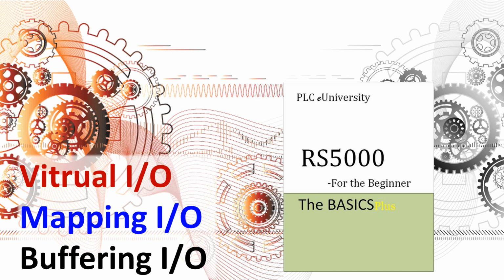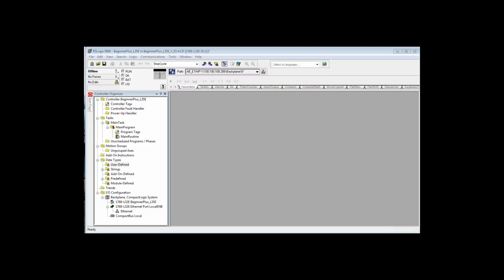And then in the course of your logic, we'll call them outputs if you like, they go to a standard integer or double integer. And when you get to the end of the program, then there's logic that transfers those output bits that you put into integers or double integers into the module-defined output data tags. That's buffering I/O.